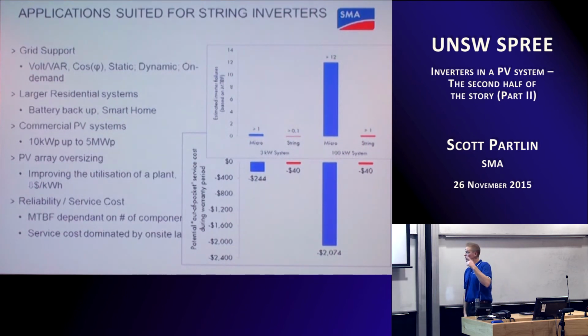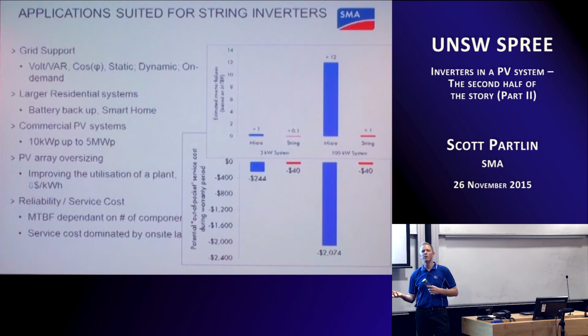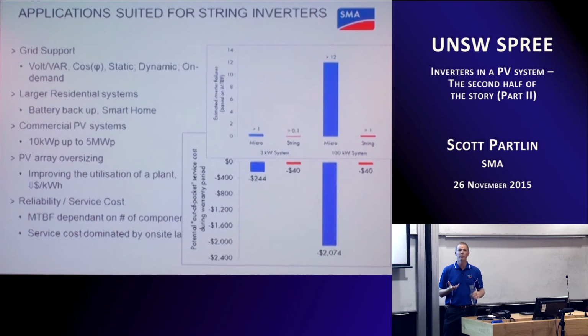I had this on the previous slide about microinverters. I'll talk about it a bit more here. But in terms of reliability, as you go to larger and larger systems, the reliability of that system is going to favour a string inverter over, say, a microinverter solution. And the reason for that is that when you do a failure analysis or a failure estimation for a plant, it will be dependent on how many components you've got in that plant, what type of components they are, and what conditions they are exposed to.